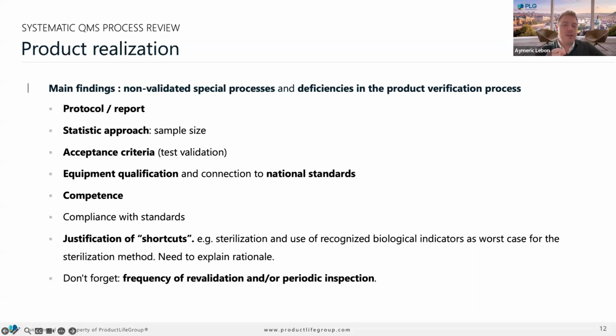Mainly for establishing your protocol, what will be your acceptance criteria? It is important to define, before doing the testing or the validation, what your acceptance criteria will be. And if you are not fulfilling them, what is the impact? Something important, especially when you are doing the validation process, is to ensure all the equipment has been qualified, and if you are doing some measurement, all the measures are done with equipment related to national standards. It is really important. Here, as I told you before, the competencies of the people in charge of this activity are checked, as well as whether there is some standard, mainly ISO standards that could be state of the art, for example.